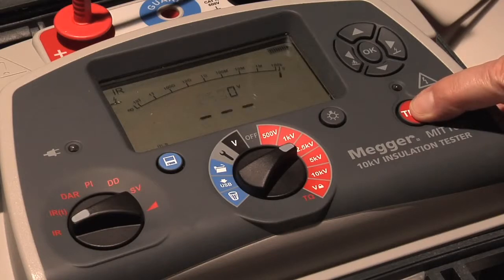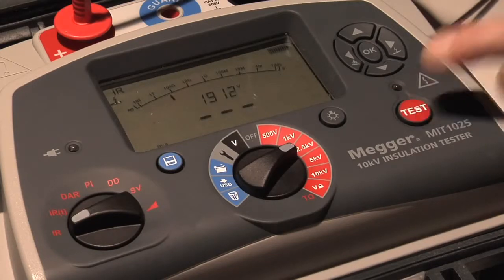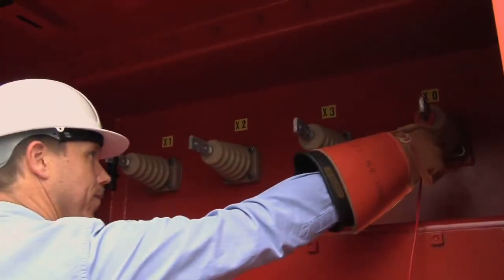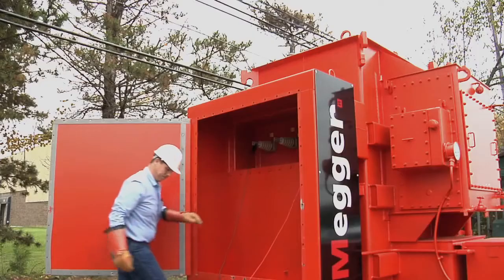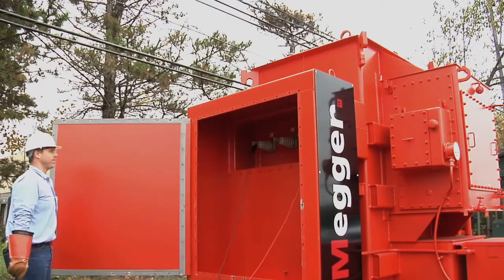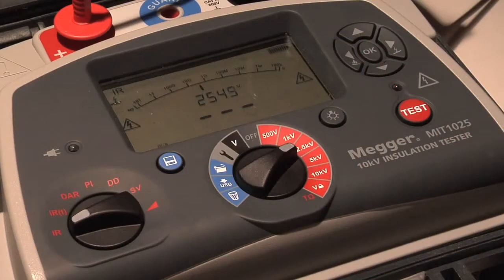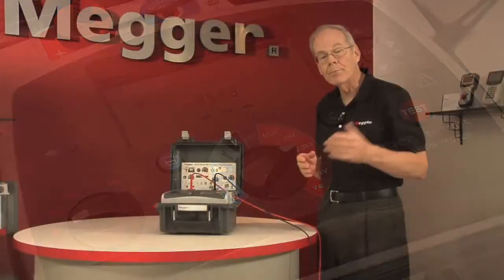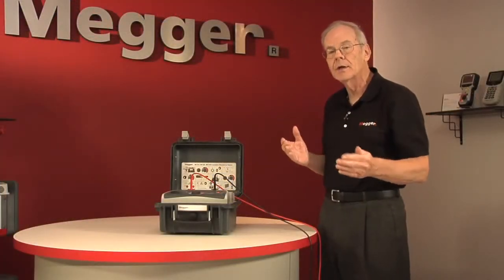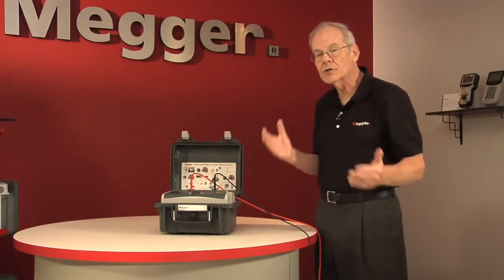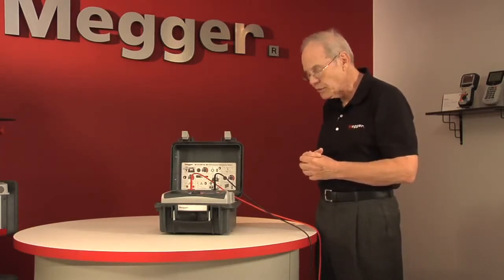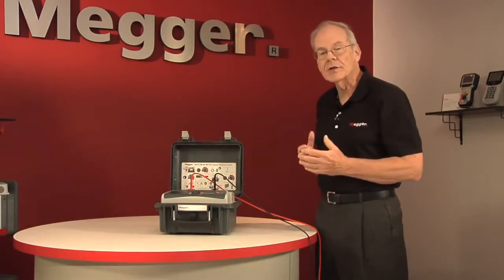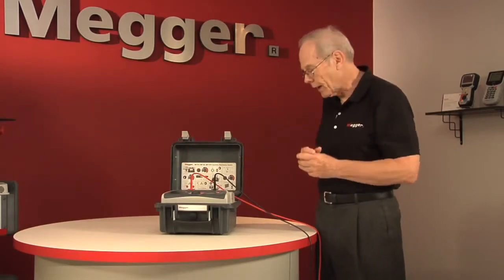It's time delayed for safety, so that in the event that your partner is hooking up the test leads, he doesn't inadvertently get shocked. And once the tester is energized, the tester then begins to apply the selected test voltage across the insulation, depending on how you've connected the leads, and measures the amount of leakage current that the insulation allows to flow depending on its condition, and it calculates out a resistance reading.